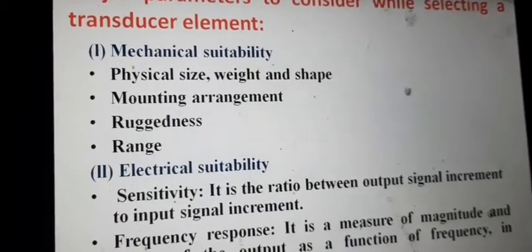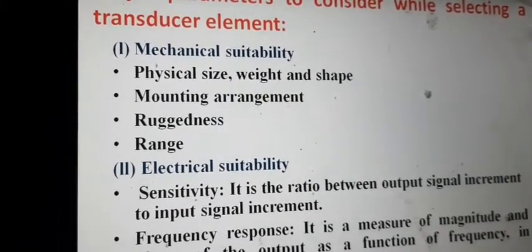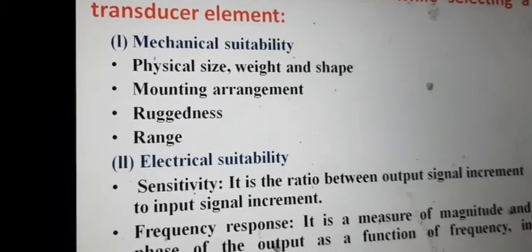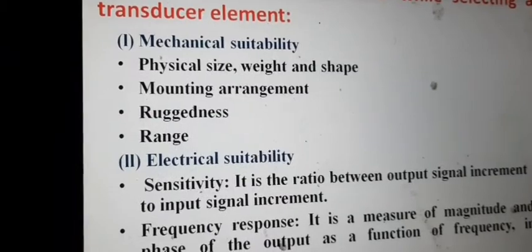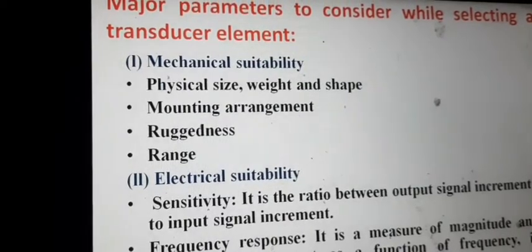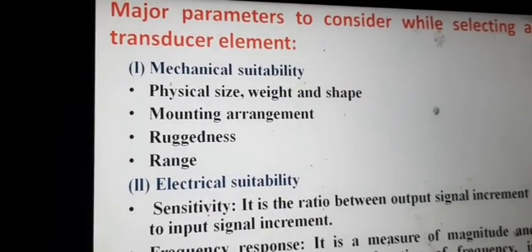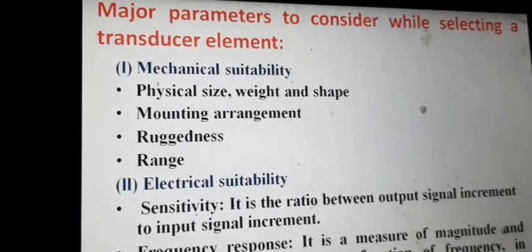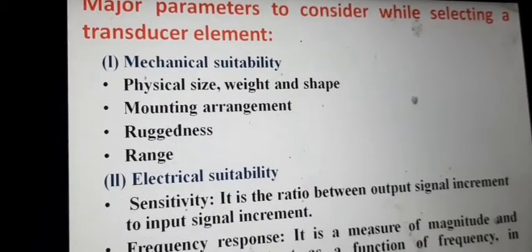From mechanical suitability, we should consider the transducer size, weight, and shape — it should be compact or small. For example, when measuring velocity we keep the transducer in the flow field, so a pitot tube or anemometer placed in the flow field acts as an obstruction. It may divert the flow field or direction, causing changes in the measured velocity from the actual velocity. So we should select a compact transducer.